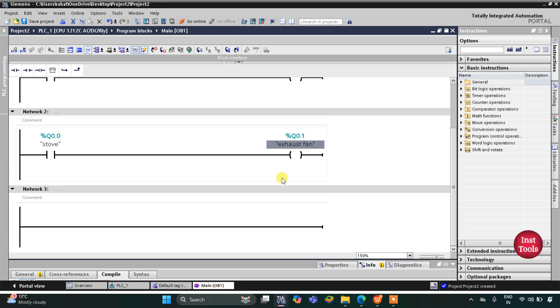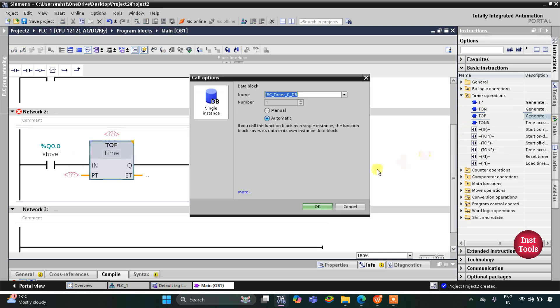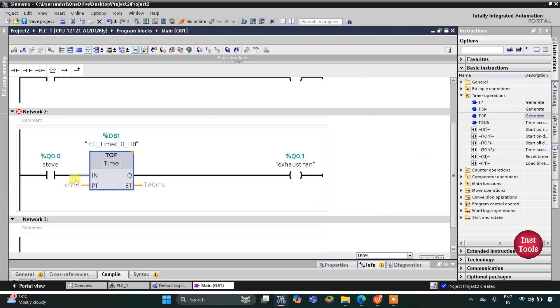When the stove is turned off, the exhaust fan will still remain on for one minute. For that we will use a timer operation — that will be TOF (off-delay timer) — and the preset value will be 60 seconds.